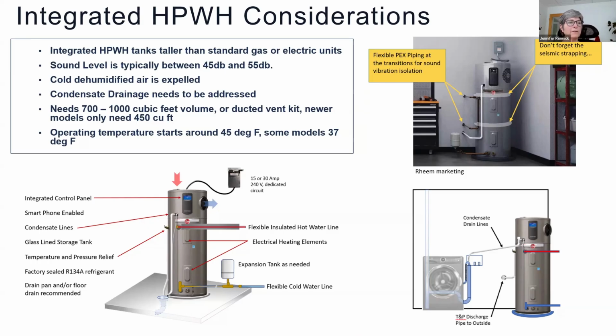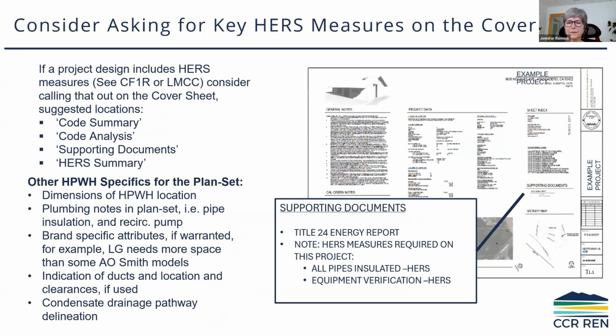So I think the point for me too is a lot of folks don't realize that's what the condensate is - they don't realize it's the same condensate you get on a cold glass of water. So as plans examiners, maybe ask them how they plan to deal with the condensate drainage pathways. But it's also good for you all to know that if there's a lot of consternation about it, it's only the moisture that's already in the air you're breathing, so you don't have to worry about it being harmful or acidic like with gas burning appliances.